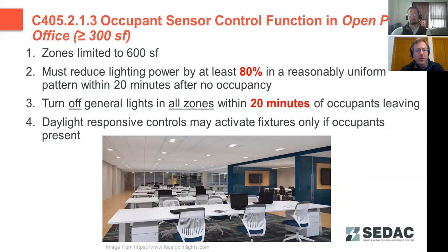And then the next requirement is you have to turn all the general lighting off in all the zones once there is no occupancy detected in any of the zones. So how these two can typically be accomplished, either you can have each zone control independently and turn off 100% of the lights in that zone, or you have to have a system where the zones are tied together so that the system can determine if there's no occupants detected in any of the zones. So those two kind of go hand in hand with each other.